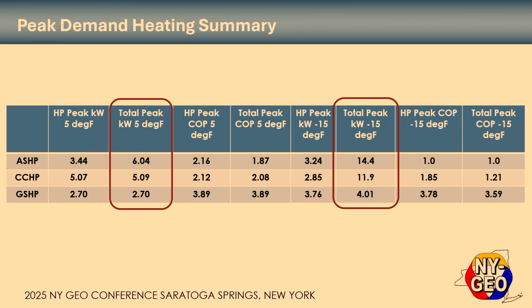It's just that I think there's a couple things that save you, right? One is that maybe temperatures drop in the house a little bit and people may or may not notice. And the other, there's thermal mass in the house. And then the other thing is diversity. If you have electric heat, we measured an apartment complex that had 75 air source heat pumps. We had the power data for the apartments. There was also resistance in the bathrooms. And we saw a diversity that was about a third of what you would have expected if you assumed all 75 heat pumps were on at the same time. So I just wanted to point out there might be a few things like diversity and thermal mass that might attenuate the difference, but geothermal is still clearly better.